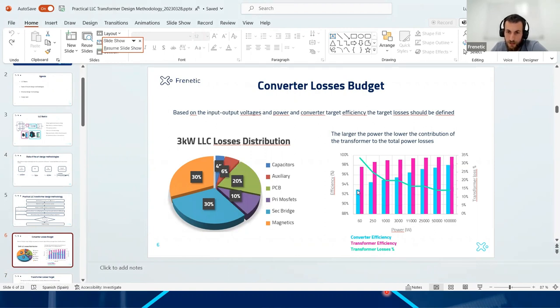Now, out of this 93% of efficiency, let's say I'm losing one third of the losses in the transformer. So this means 33% of the total losses are in the transformer. And this is the transformer efficiency. So the transformer is 98% efficient, but overall, it takes 33% of the losses. So let's put some numbers. If I lose 10 watts, I lose 3.3 in the transformer. Out of the total efficiency of the converter, it would be 98% efficiency for the transformer, but with respect to the total loss budget, you are losing 30%. That's how this plot should be interpreted.